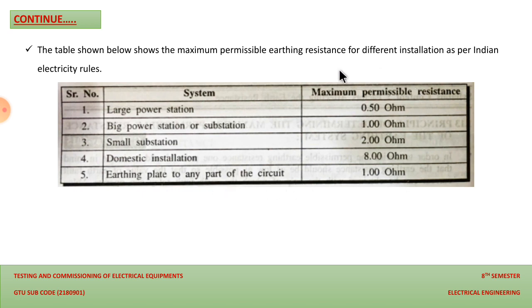So this is the maximum permissible resistance as per the Indian Electricity Rules that we should keep in mind while providing the earthing. This is the permissible resistance that we should keep to protect our system from the fault. So this is how we can discuss the factors which affect the soil resistance, and the points that we should keep in mind while providing the earthing.